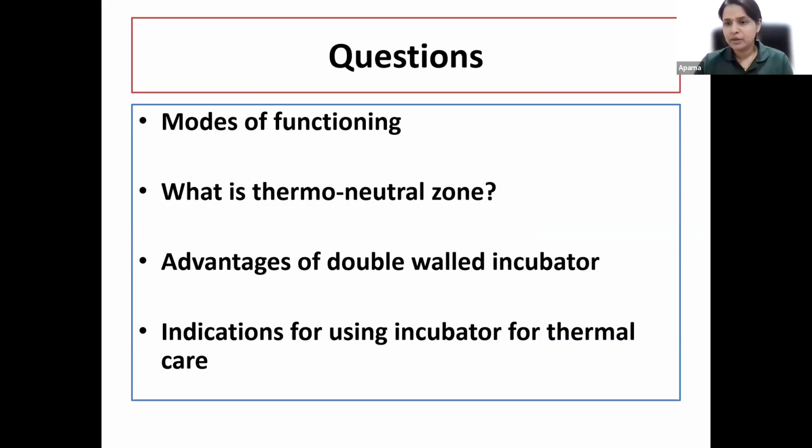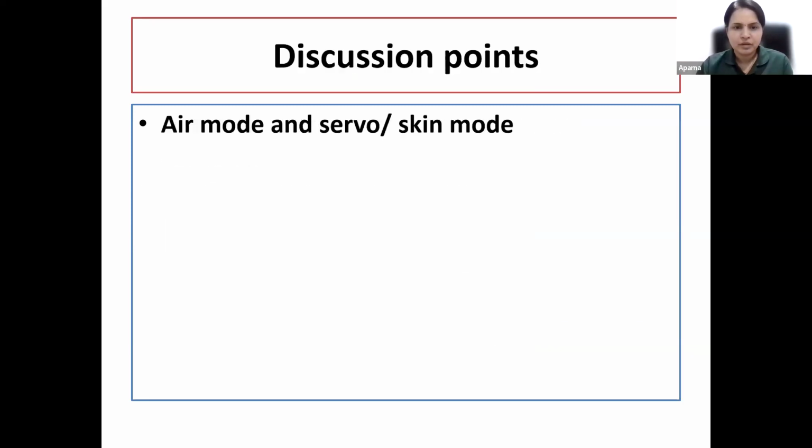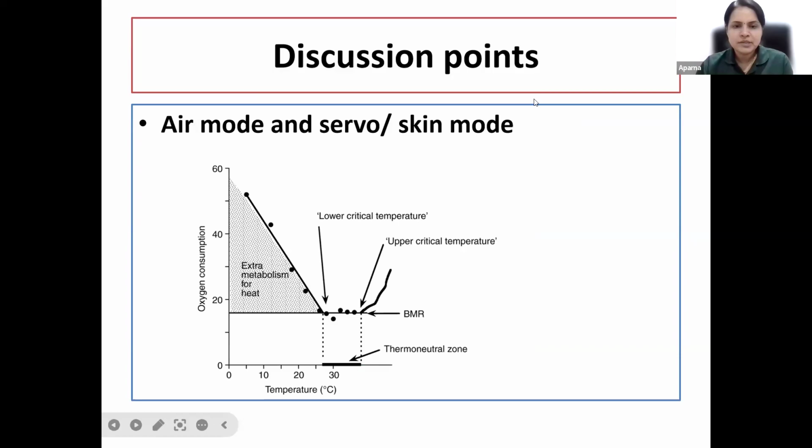We just discussed that the incubator works on the principle of convection, and the two modes are the servo mode or the baby mode, as well as the air mode. What is the concept of the thermoneutral zone? So I'll explain this with a picture.